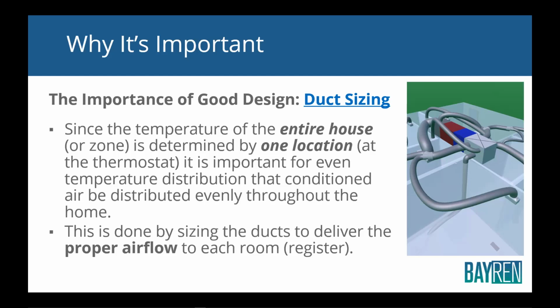And that's a load on the entire house or the entire zone if the house has more than one system. But when you're sizing ducts, you have to do room by room load calcs because you need to know what the load is on the master bedroom compared to the kitchen, compared to the living room, compared to one of the other bedrooms. Each room is going to have its own load, and each room's load is going to be a percent of the total.